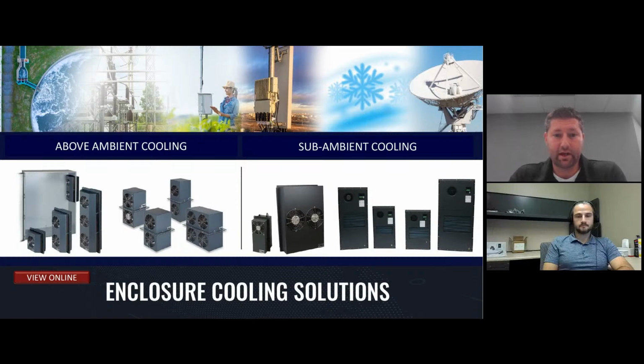And then the sub-ambient cooling options, there's again two options within that spectrum. If you need to keep your cabinet lower temperature than your air, the two options are: the one on the left is the thermoelectric cooler, which uses Peltiers or thermoelectrics to provide solid state cooling, and on the right is the more traditional air conditioner using vapor compression to provide sub-ambient cooling.